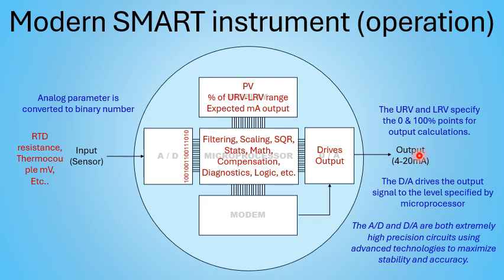Sometimes you don't have to do that, for example, on fieldbus instruments, or depending how your maintenance is laid out. Sometimes you're just checking this part. But if you're just checking the PV, know that you have not checked this, and you will occasionally need to check the rest of that signal. And it even can fail and drift and everything along the way.